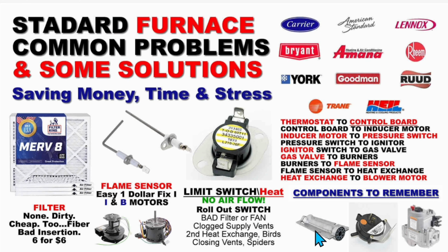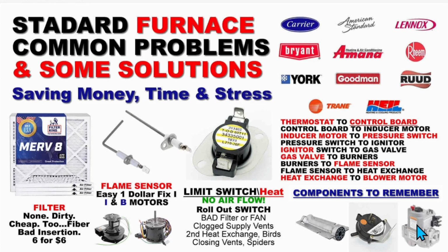The in-shot burners, you normally have 4 or 6 of these, but these get dirty and clogged up. And again, if you don't change your filters, it gets even worse. And this causes problems as well. So keep those clean, kind of air them out, take a wire brush, clean them out. Your pressure switches, they get stuck sometimes on open and closed. If that happens, you just have to replace it. Not much you can do. Your gas valves, you have to replace those sometimes. And normally if you put in a new gas valve, you have to set the pressure to about 3.5 or so. Just do some research on that. Look at your manual, but you need to adjust that gas pressure. And that could cause errors as well.